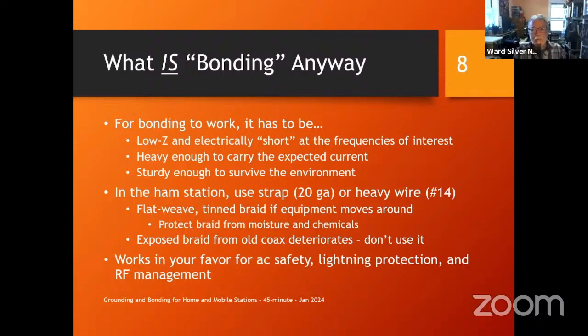If you're talking about bonding for lightning protection and you're talking about your antenna system, you have to have big wires, what I call the BAW, big ass wire. That's why they're so big. They have to carry kiloamps. To a circuits guy, the concept of kiloamps is scary to me, and it should be because there's a lot of energy there. And in a lightning strike, even an indirect surge, you can get a lot of current. So the bonding conductors have to be heavy enough to carry it without vaporizing.